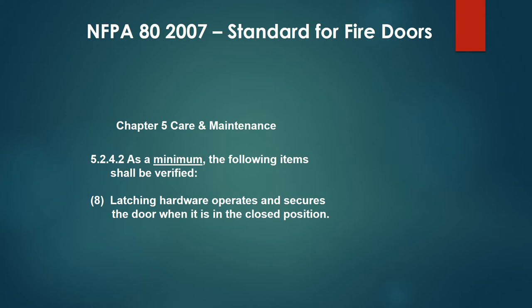Building pressurization is an interesting issue. If you have a long corridor with doors on either end that are open — due to traffic, hot weather, or move-ins — and building pressurization changes, you can almost guarantee doors inside the building will no longer latch. This is also something to be mindful of with stairwell doors. Requirement number 9: auxiliary hardware items that interfere with or prohibit operation must not be installed — glove holders, foam dispensers, or anything placed near a door that could interfere with its operation or opening swing.